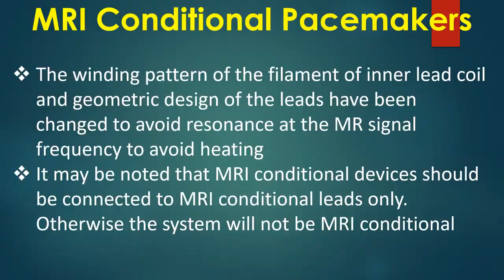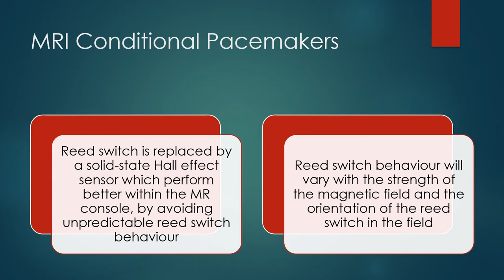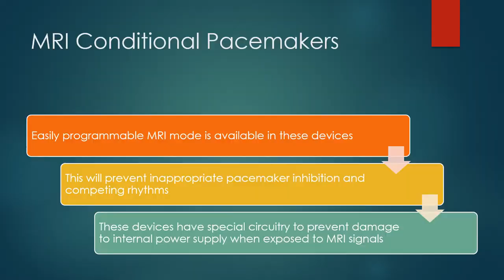Reed switch is replaced by a solid state Hall effect sensor which performs better within the MR console by avoiding unpredictable reed switch behavior. Reed switch behavior will vary with the strength of the magnetic field and the orientation of the reed switch in the field. Easily programmable MRI mode is available in these devices. This will prevent inappropriate pacemaker inhibition and competing rhythms. These devices have special circuitry to prevent damage to internal power supply when exposed to MRI signals.